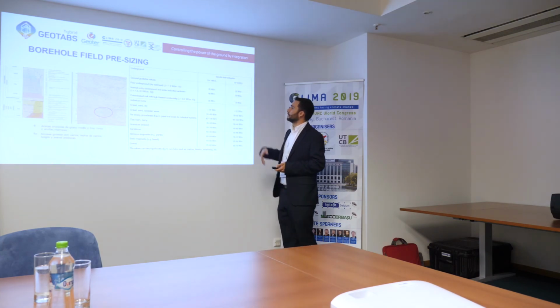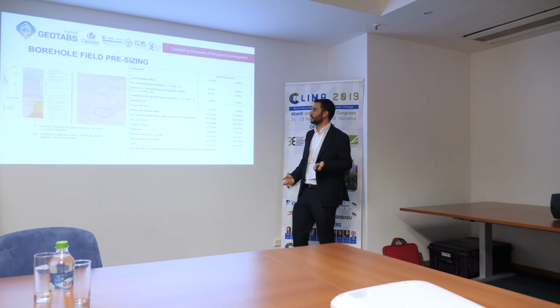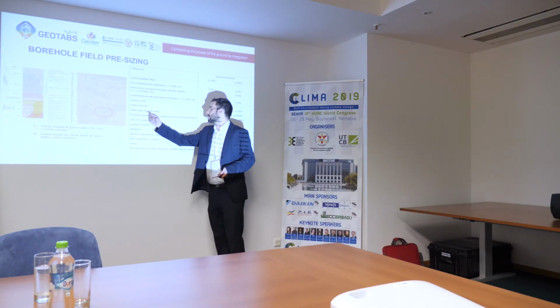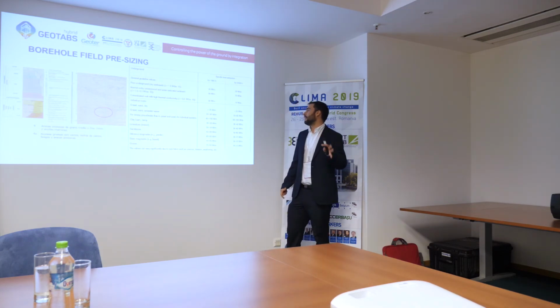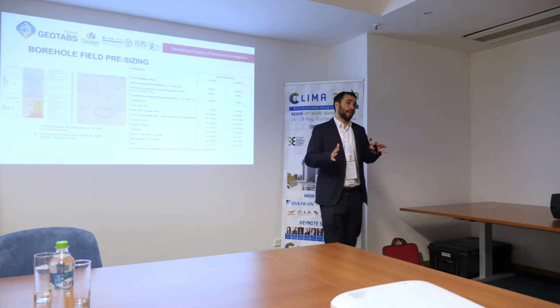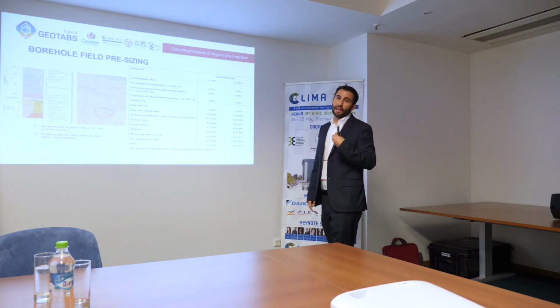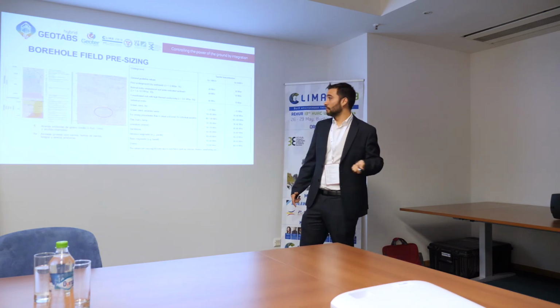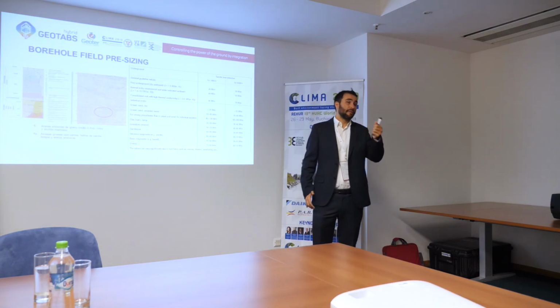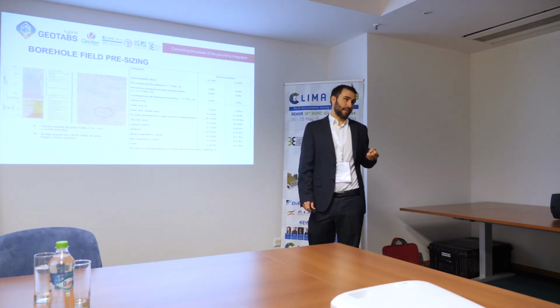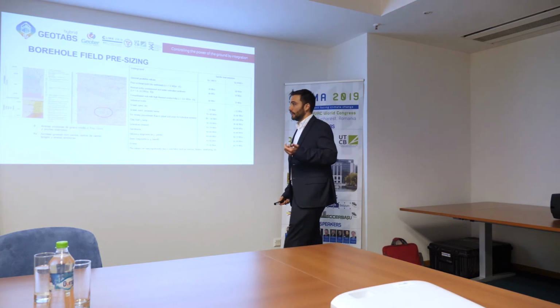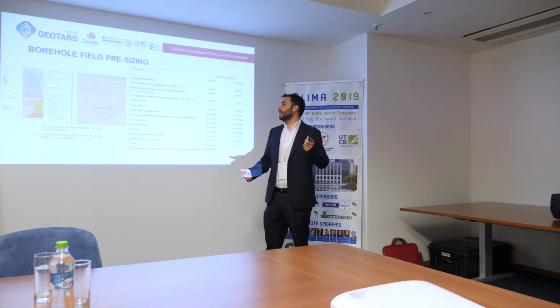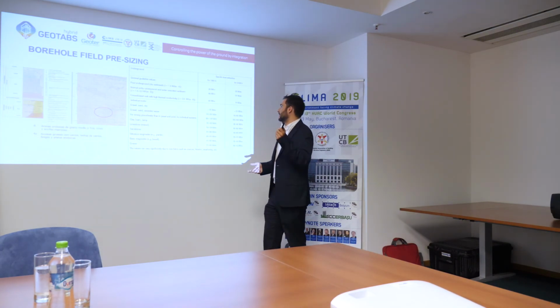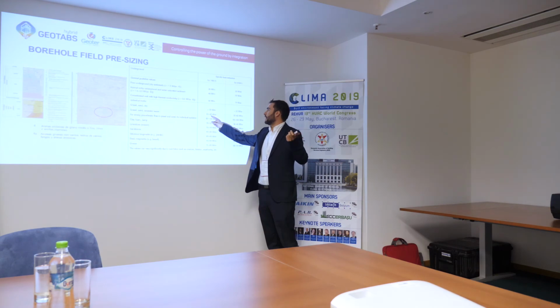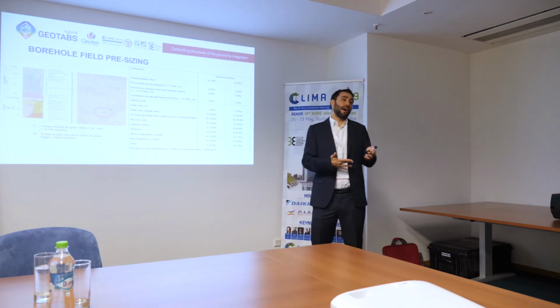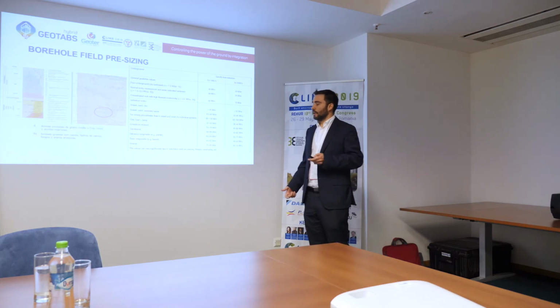So I can go to this table about the specific heat extraction, and I can see that, for example, for gravel and sand saturated with water, I have around 65-80 watts per meter. It's a rough estimation. So if my house needs a 10 kilowatt geothermal heat pump, that means with a COP of 5, I am going to obtain 80% of the energy from the ground, and the rest is electricity. So I have to obtain 8 kilowatts from the borehole site. If I have around 80 watts per meter, I need 100 meters for my geothermal exchanger.